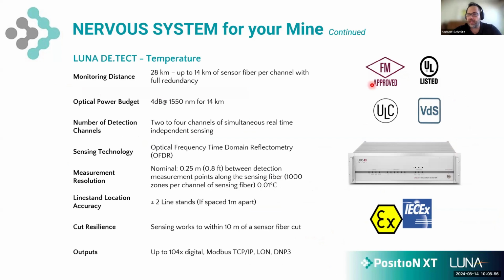These systems are fully FM, UL, VdS certified for fire detection application. And additionally, we have the option for ATEX or IECEx certification within the coal mining or confined space environment where we have explosive dust or gaseous environments. And we have various systems. For the temperature fire detection certified systems we have options up to 14 kilometers per channel, and where fire certification is not required, we have up to 70 kilometers per channel. And we can have systems with resolutions down to 25 centimeters and a temperature resolution down to 0.01 degrees Celsius.